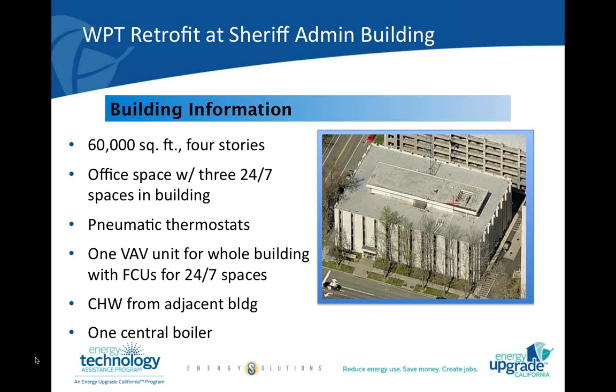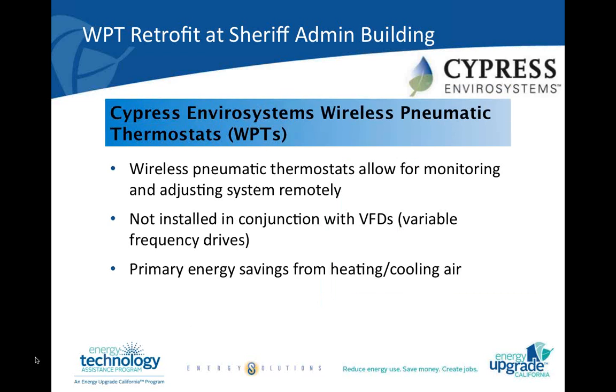Next slide, please. So as mentioned, this would be the Cypress wireless pneumatic thermostats. A lot of great things, a lot of promise associated with this piece of equipment. We've actually had a chance to get one early on and install it and play with it a little bit. It was just doing local control. Seems to work okay. There are some concerns about calibration. It's a very sensitive piece of equipment, but there are a lot of lockout features associated with it also. And it wasn't that hard to get a sample, so if you're looking at doing one of these projects, definitely talk with your local suppliers and see if you can get at least a single thermostat or possibly get a trial system where you can communicate with it through your local network.